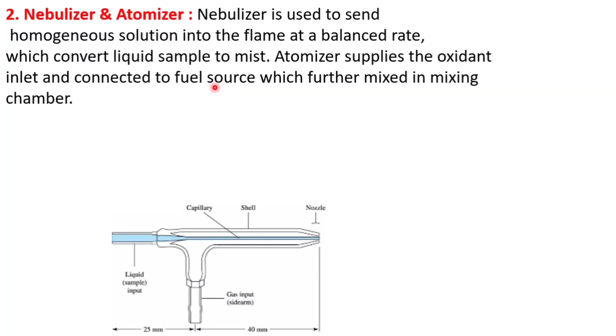Second one, nebulizer and atomizer. Nebulizer is used to send homogeneous solution into the flame at balanced rate, which converts liquid sample to mist. Atomizer supplies the oxidant inlet and is connected to fuel source, which is further mixed in the mixing chamber.